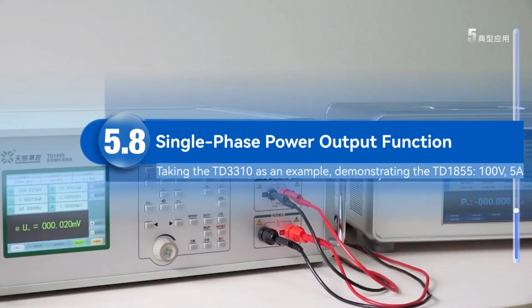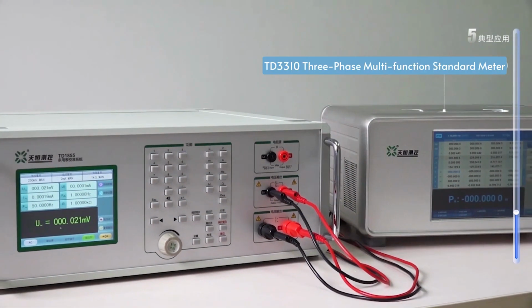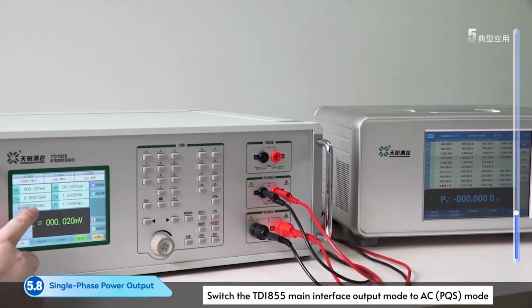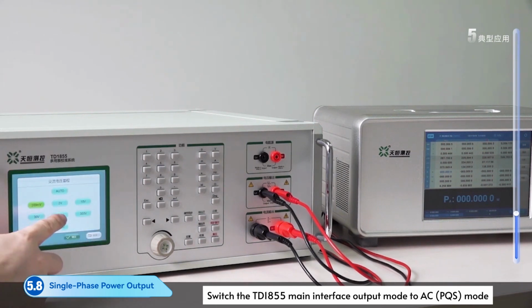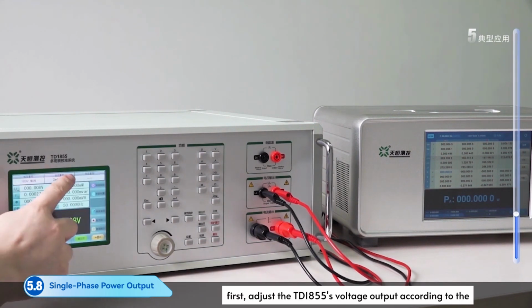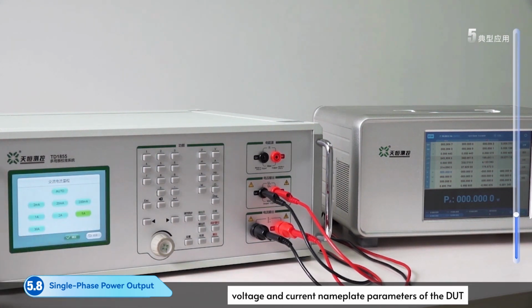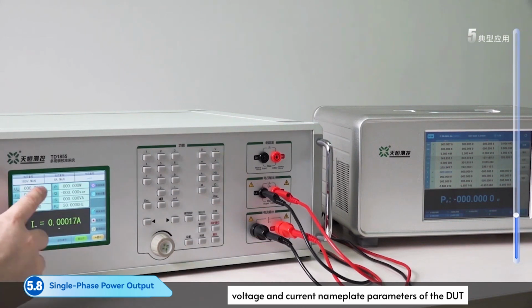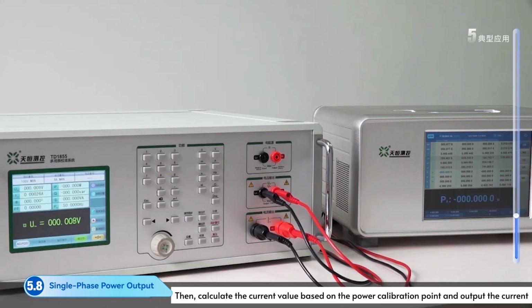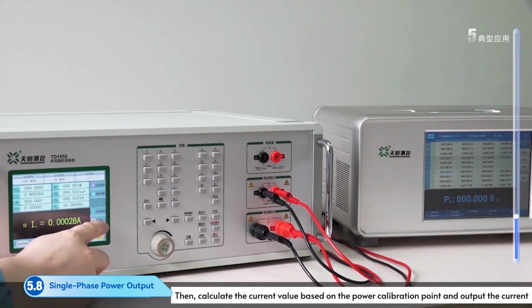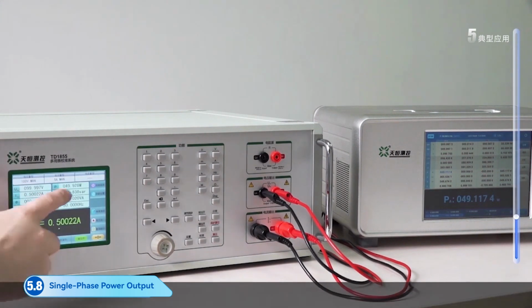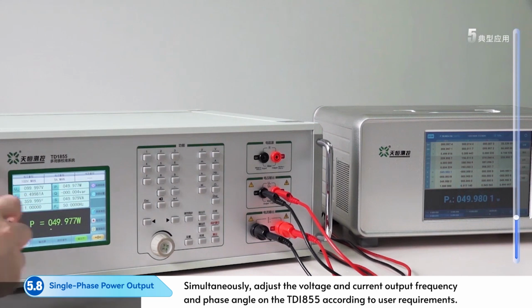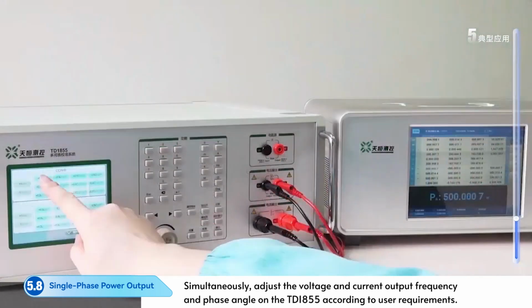Part 8. Single-phase power output function. Switch the TD1855 output mode to AC (PQS) mode, based on the calibration points. First, adjust the TD1855's voltage output according to the voltage and current nameplate parameters of the DUT. Then, calculate the current value based on the power calibration point and output the current. Simultaneously, adjust the voltage and current output frequency and phase angle on the TD1855 according to user requirements.